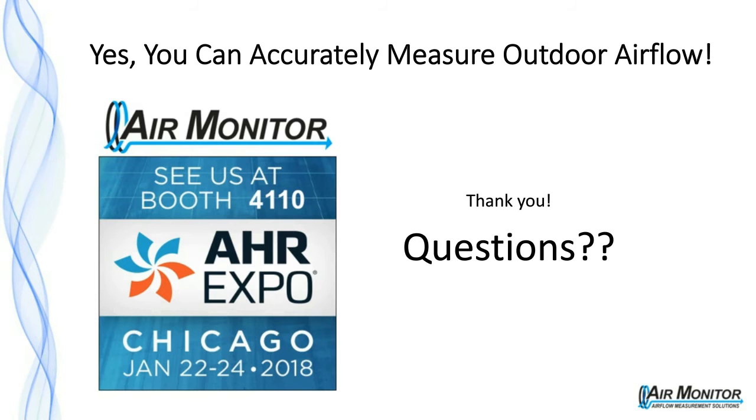Okay, I'll take another question that came in. It asks, do you use louver total area or free area? And the answer is the relation that we use in determining the flow rate range is based on face area of the louver, and or the inlet. And there's a reason for that. In most cases, we are always looking at total CFM in terms of the opening itself as it comes through. Louvers themselves have published free area, some louvers do, but in many installations there is not a published correlation between that free area of the louver and the face area. It's also something that when we're trying to determine the best geometry to use in terms of where sensors are placed, we want to look at the total face area, rather than the free area, and stick with something that is known.